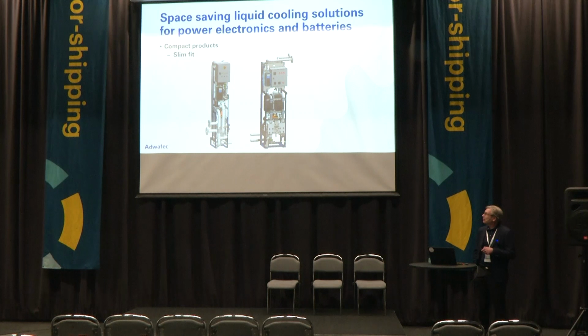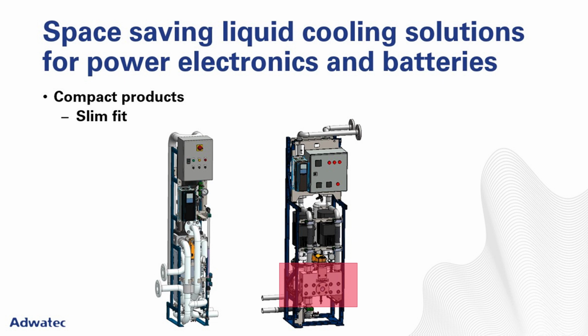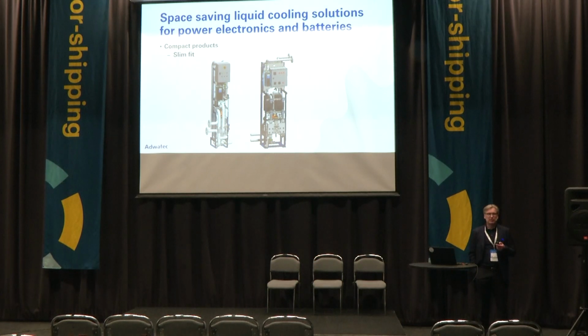We have this manifold block here, created for these cooling systems. The idea is to get rid of some pipe components, because when using pipes to create the needed functionality in this kind of cooling system, you need quite a bit of space for all the bending and adding the different components and instrumentation needed. With this manifold, we can get rid of all that and really reduce the size of this cooling unit so that it's not a lot more than the size of those pumps next to each other.